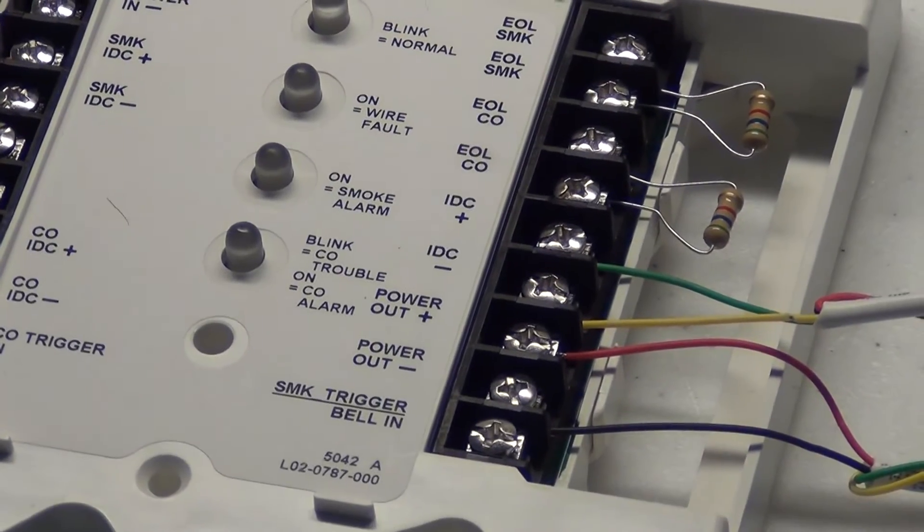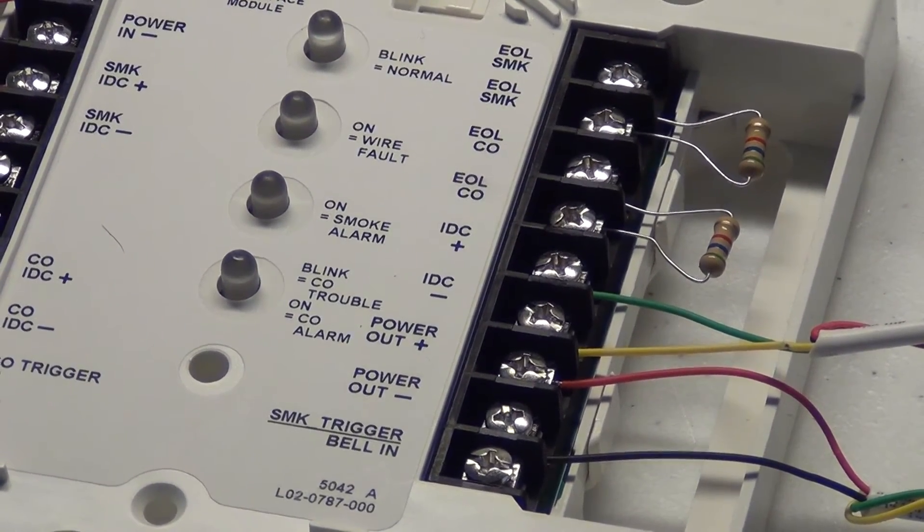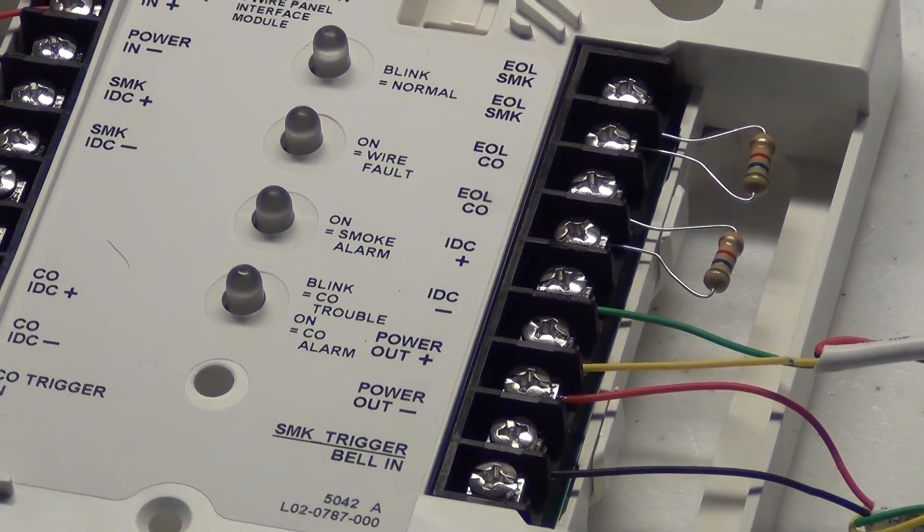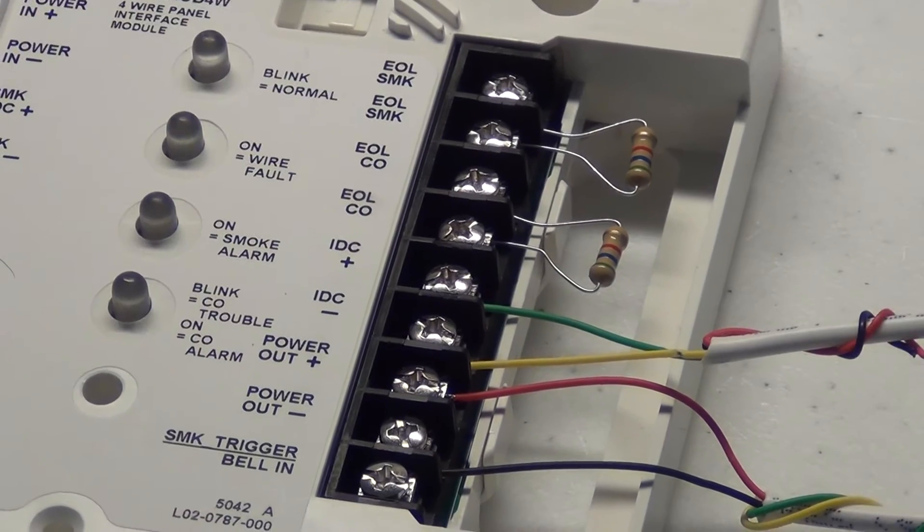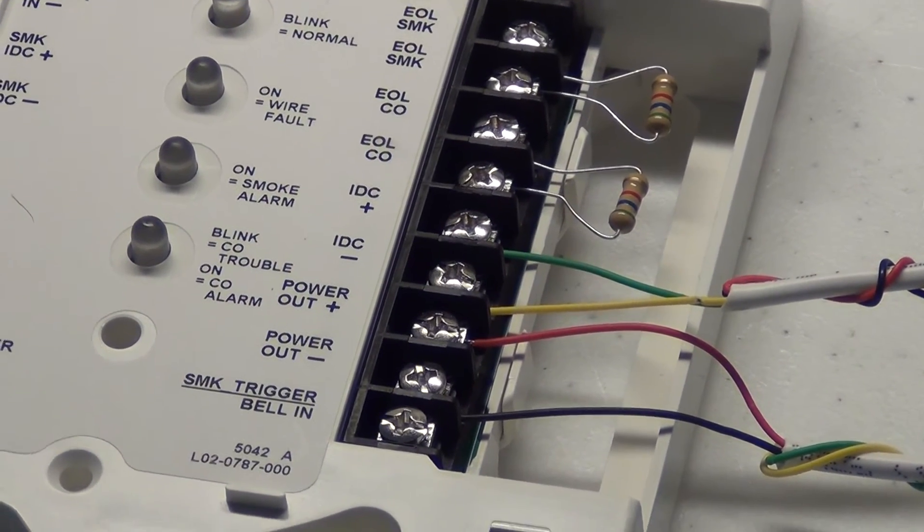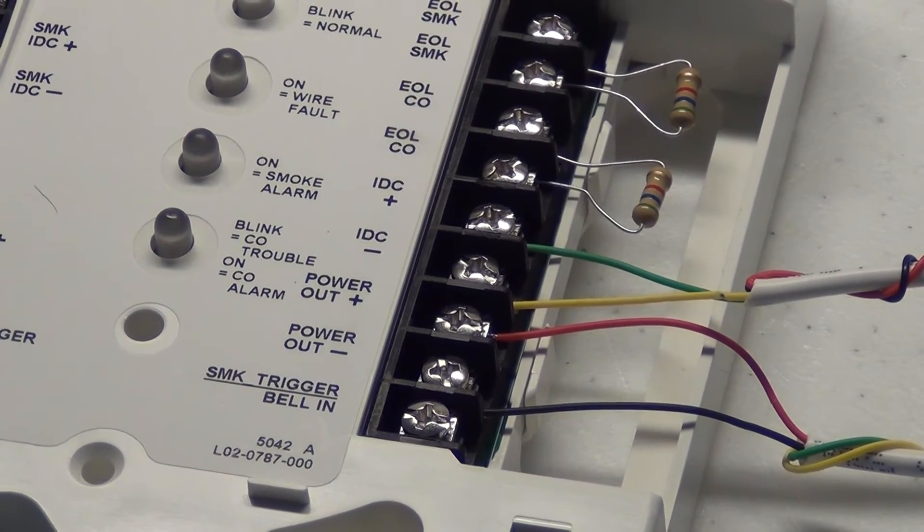Over here on the right hand side you will see we have wiring terminals to connect over to your smoke CO combo units. These two spots up here are for your end of line resistors. I've just got some in here for example but you will use whatever value of resistor your alarm panel calls for.